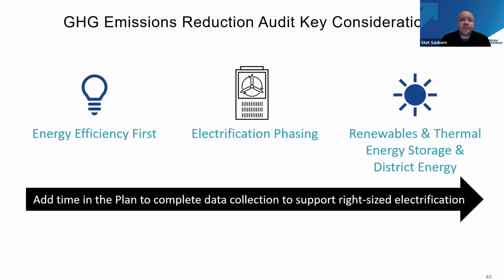As Jess mentioned, we want to focus on efficiency first. I see a lot of chat about people thinking their building's heat pump won't work—it might not be the right heat pump for your project, but I guarantee there is a heat pump that can work for it. Before we throw a heat pump at it, what other efficiency measures can you deploy? Envelope upgrades are key in cold climates, especially focusing on infiltration and leakage, since we waste a lot of energy letting heat leave our buildings. Phasing this work as part of an envelope upgrade will also help you downsize those heat pumps.